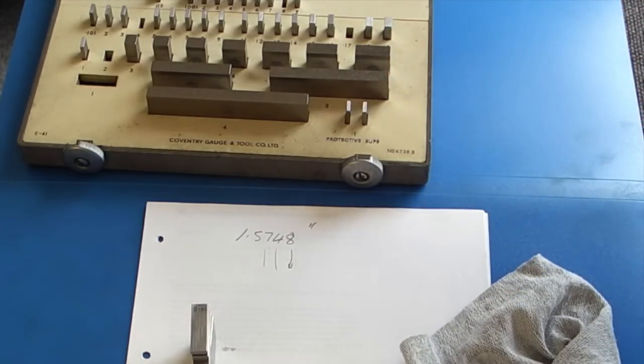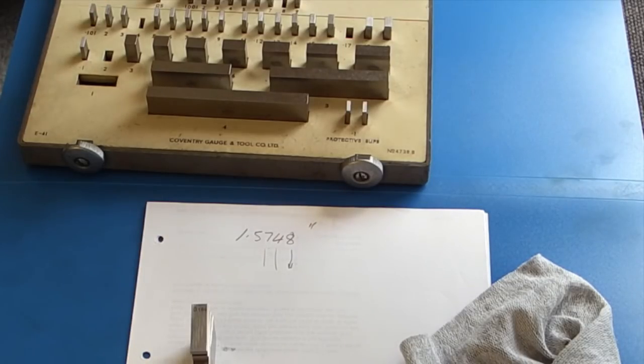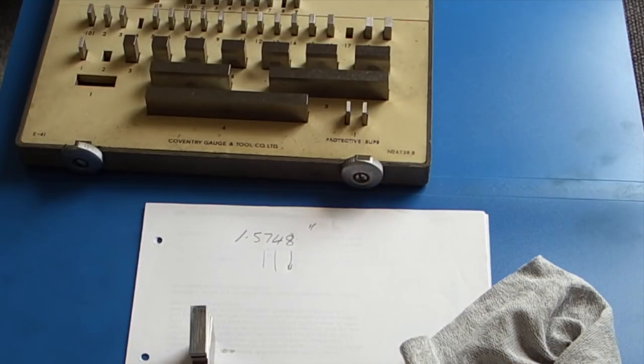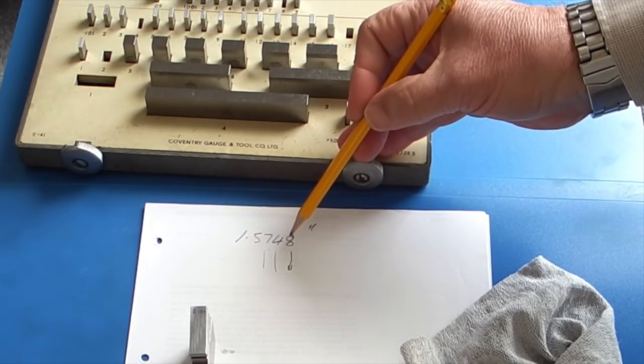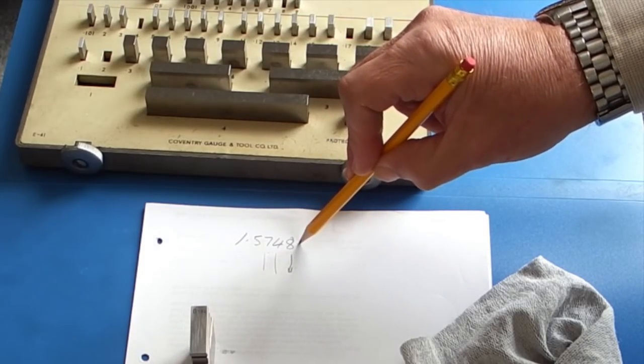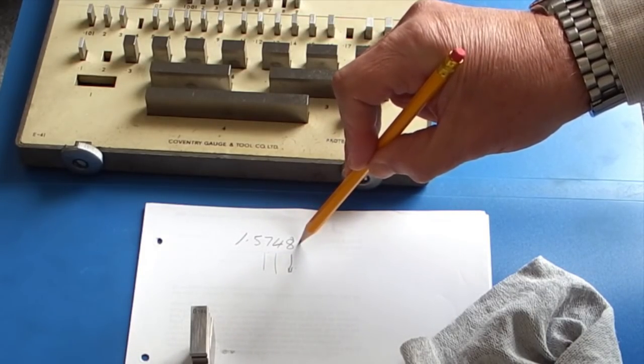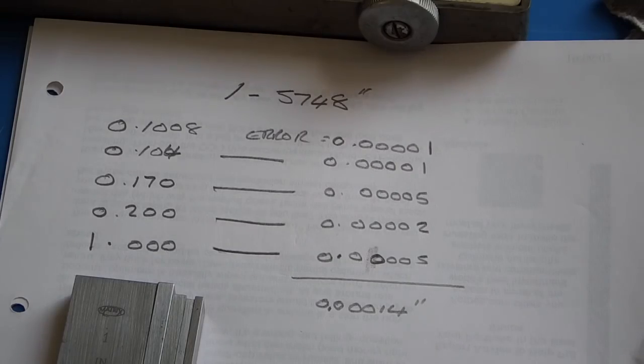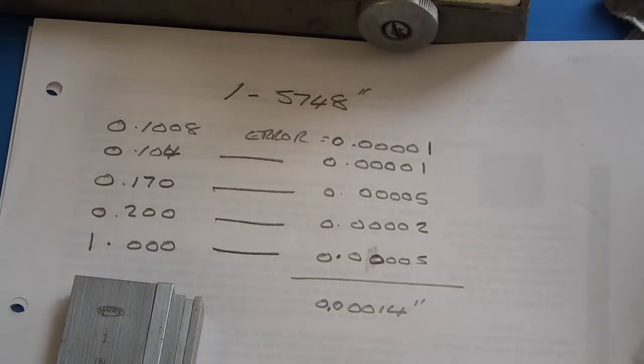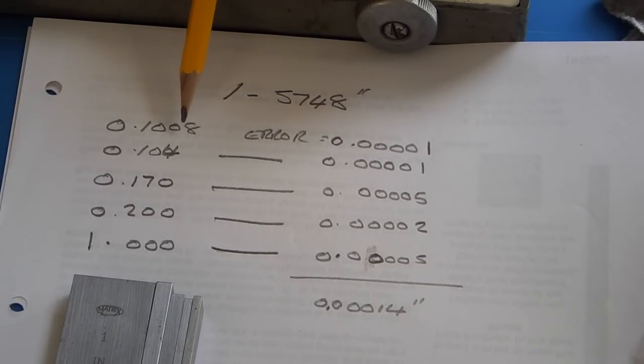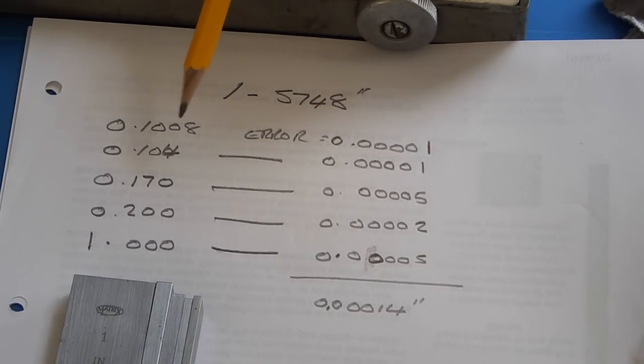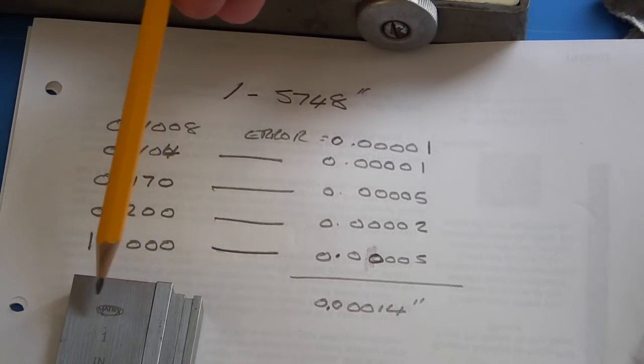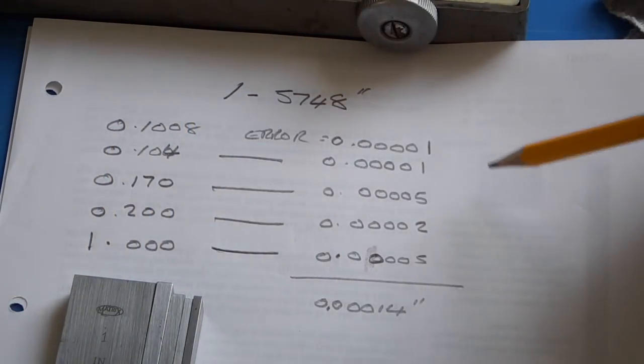The calibration certificate should give you each block listed, what it should read, and what the deviation is from the stated size. Normally the deviation will be a minus from the original size because the blocks do wear out. I think it would be quite rare to find a block that was oversized. So assuming that your calibration certificate gave you this, that the 0.1008 had an error of minus 0.00001, and the other blocks that we've used to build up this size 1.5748 had these errors.